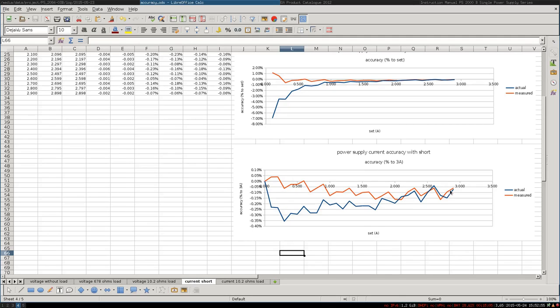Then it just crosses there, and it never reaches zero. In the beginning it always undershoots, and it overshoots the current that is measured, but not long ago, after 0.25 amps, you can see that you are always lower. So what is measured and what is really output is lower than what is set.